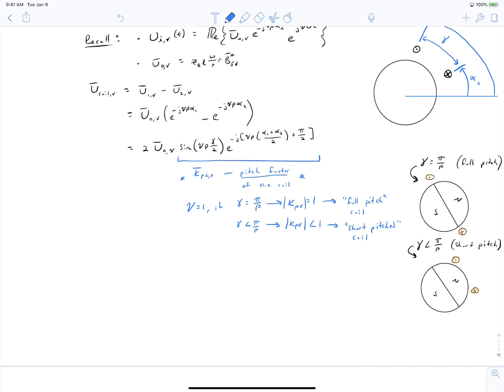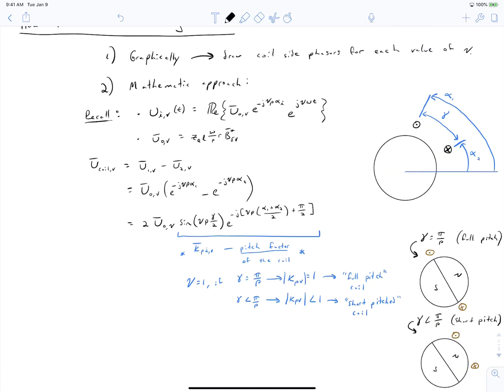You can immediately see that the coil pitch affects our winding factor — it affects the magnitude of our back EMF. If the sine term decreases, the magnitude of our coil's voltage also decreases. The reason we do this is that by carefully picking gamma, we can eliminate certain harmonics: certain values of v will have the sine equal to zero, while our fundamental component at v equals 1 might remain close enough to one that we are still satisfied. That is what the pitch factor means and how it relates to whether the coil is full pitch or short pitch.